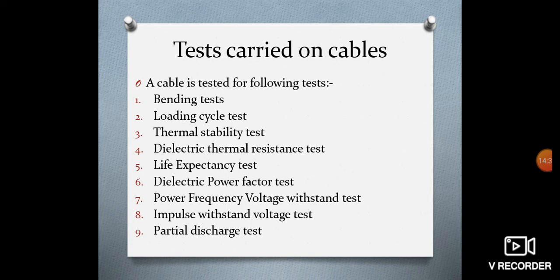Dielectric thermal resistance test. The ratio of the temperature difference between the core and the sheath of the cable and the heat flow from the cable gives the thermal resistance of the sample of the cable. It should be within the limits specified in the specifications. Next, we have the life expectancy test.